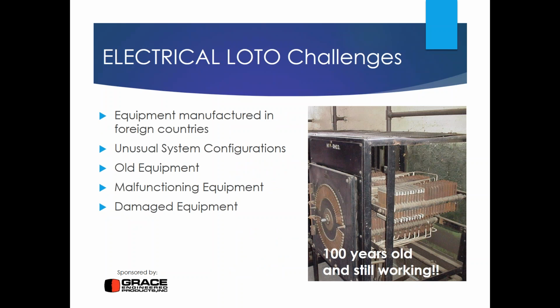In terms of some challenges, well, there are several. Since January 1st of 1990, everything in the U.S. has to be lockable by design to accept the lockout lock. Of course, now in our global economy, many countries produce electrical equipment that is not lockable. So in those situations, of course, you'd have to use that 2 conscious act rule, right? You'd have to do something equivalent to a lockout system.